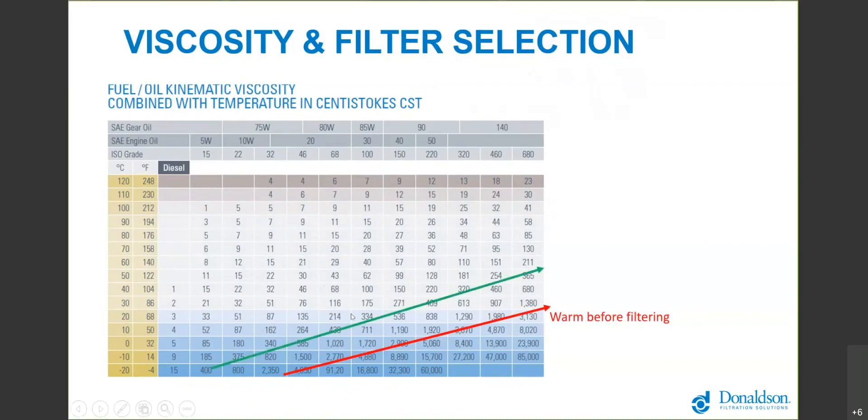Between 300 and 1,700 centistoke viscosity, we like to use our heavy oil filter which will get an ISO target of 18/16/13, and that's the part number DBB 8664. We sell a high viscosity cart that maxes out about 1,700 centistoke with four filters all plumbed in parallel.